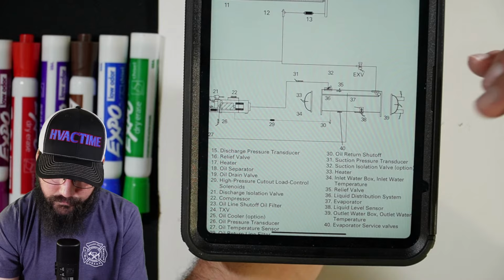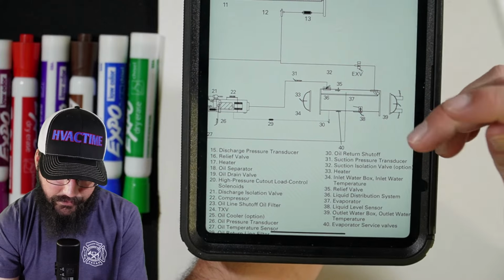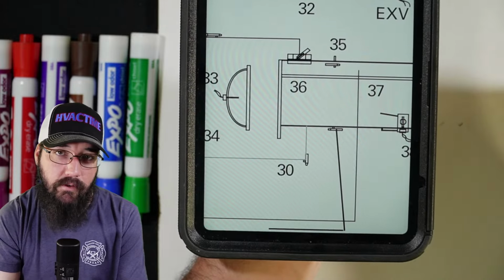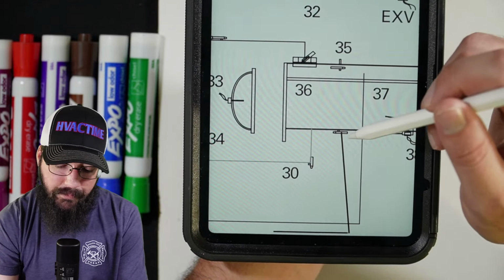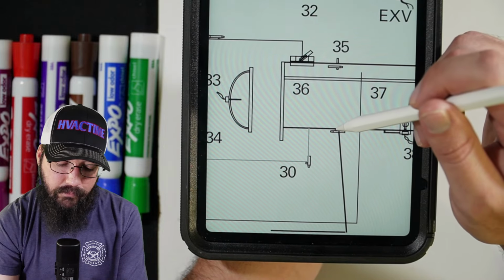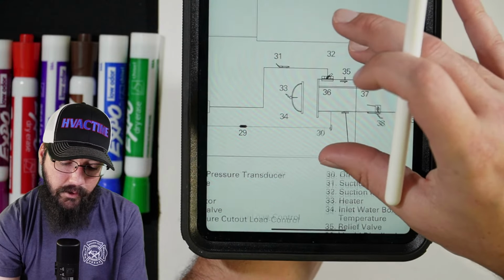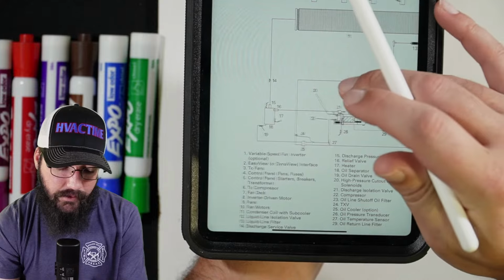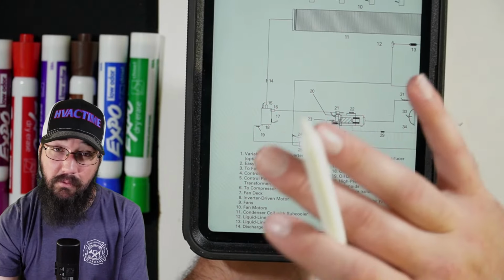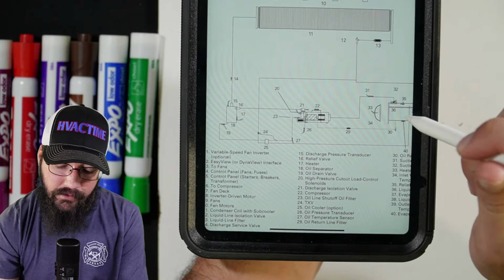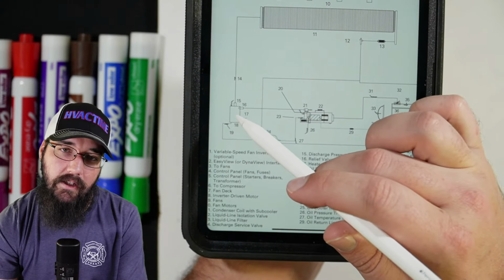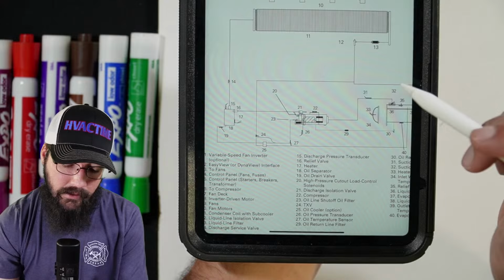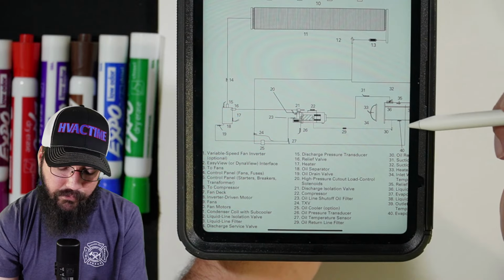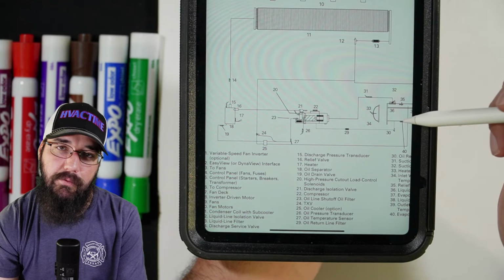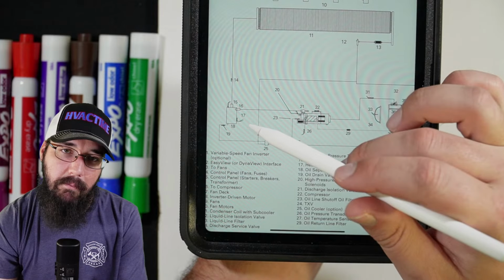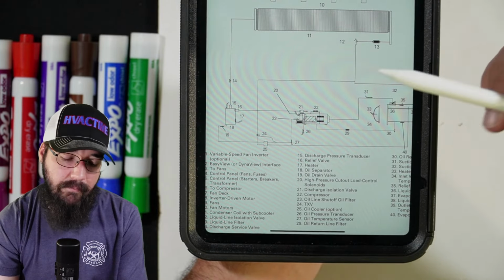So, yeah, I mean, worst case scenario, you can see where it notates. It has a service valve on the bottom of the evaporator where you can recover from. If you really had to, something you could do is try to, say, recover that oil with a recovery machine back into, like, over here on the high side of the system or something. I'm really not a fan of that, but let's say you were in really worst case scenario. The trouble is, whatever liquid refrigerant, you don't really want that liquid refrigerant over here. You really, really don't want it over there. But again, if we were in a really worst case scenario, because I'd hate to trash this just because of that migration, the idea would be, okay, well then let's just move it back over to the high side. We'll have to mitigate managing that. Here's the problem.